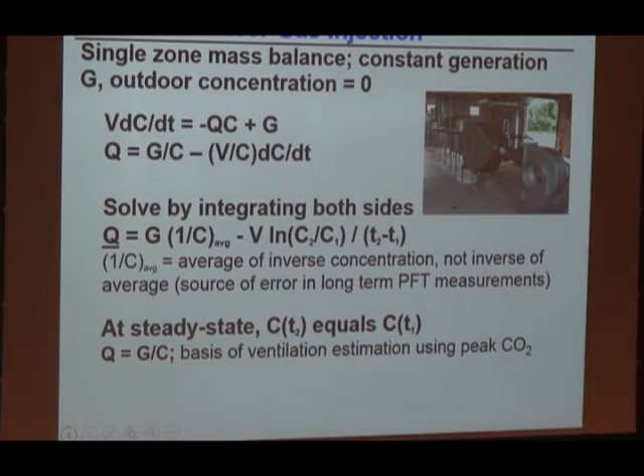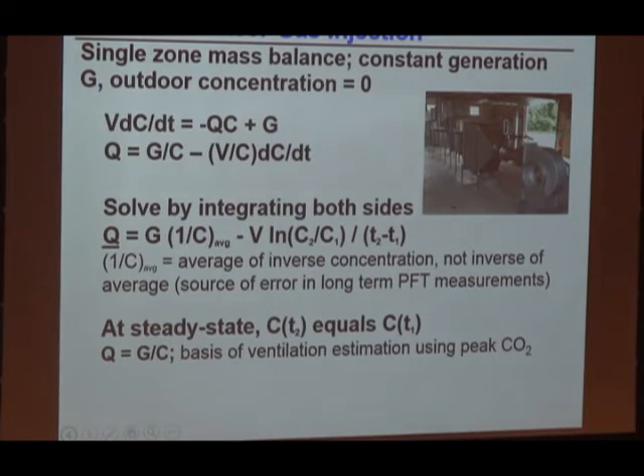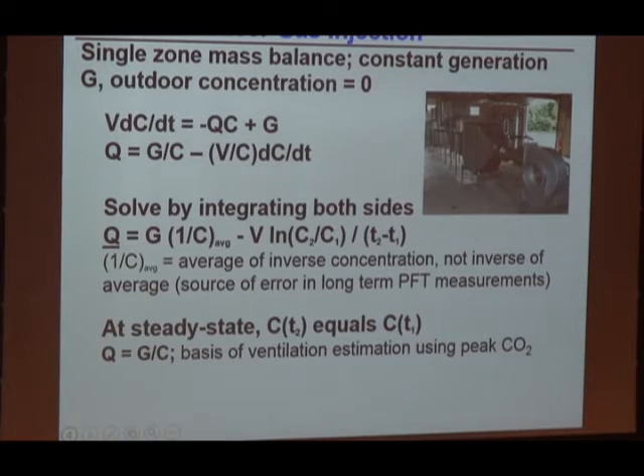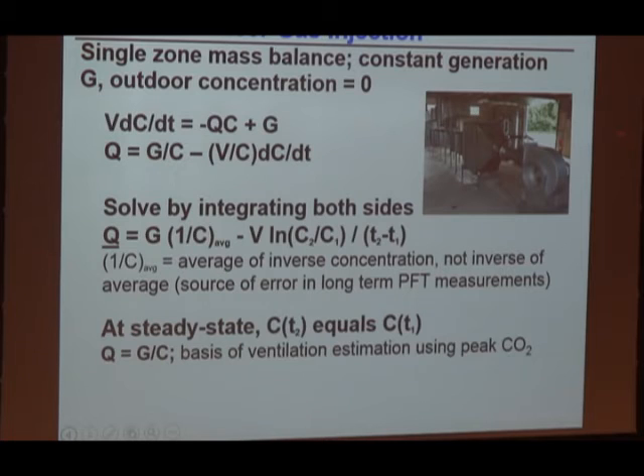The constant injection technique involves injecting the tracer at a constant rate and measuring the concentration. In some situations this is a very appropriate technique. It's the basis for the long-term PFT measurements that have been around for several decades — though there is an inherent bias in those long-term measurements that you need to be careful about. This is also the basis for using peak CO2 concentrations to estimate ventilation rates, which I'll discuss next. It can also be a very useful technique for measuring flow rates in ducts: inject at one end and measure concentration further down.